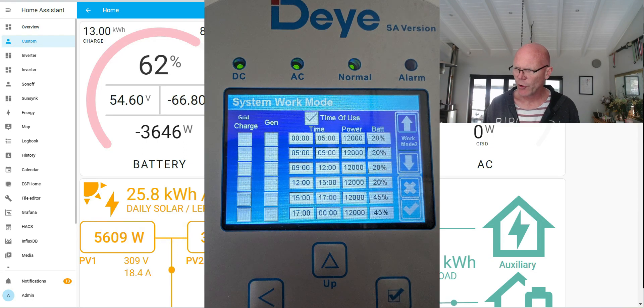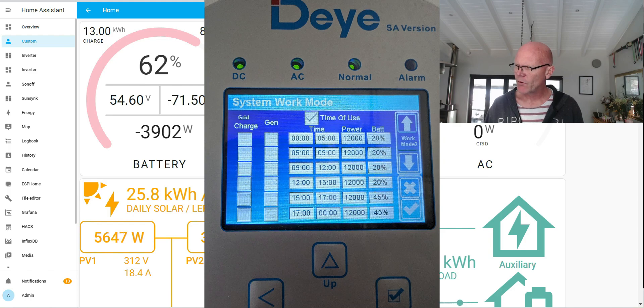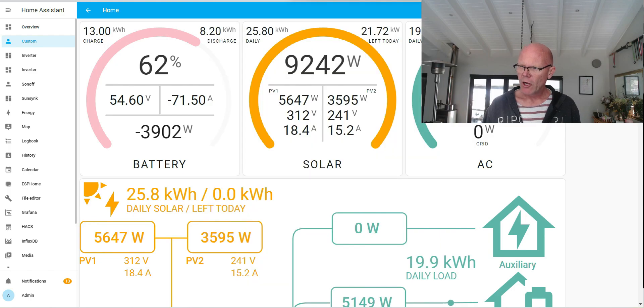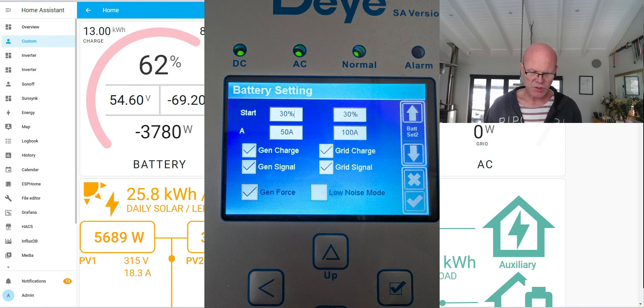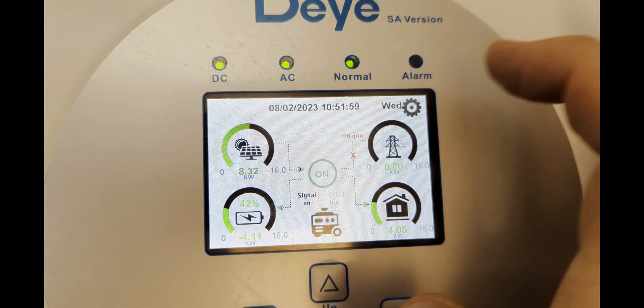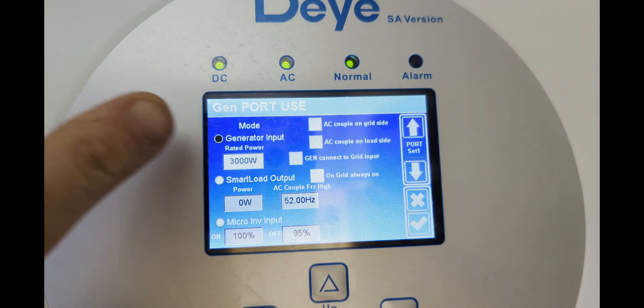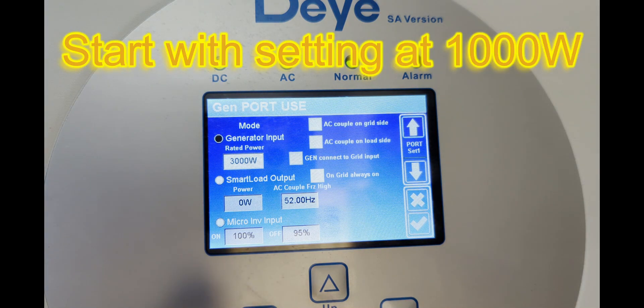These are the settings on my system. Work mode — as you can see I don't have any of the grid charge boxes ticked, I assume that's for if you want to have the ATS port kicking in. On my battery settings menu I've got gen charge, gen signal, and gen force boxes ticked. My understanding is that the gen force box sets the inverter to charge from the generator no matter what the work mode settings are, so you don't need to go and tick all the boxes on the work mode settings. Under gen port use you can set your maximum load — mine's set for 3000 watts with a 5.5 kVA generator.